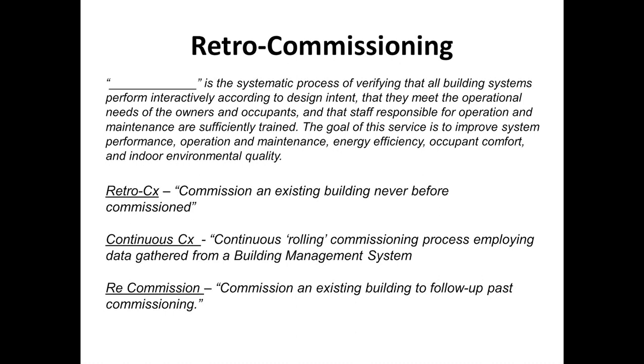There's continuous commissioning, and that's implementing a rolling commissioning process, such as using a building management system or trending data to really keep track of implementations that have been made and continuously make improvements in a building. And then there's recommissioning of a building. That's a building that's already been commissioned, and looking back at those original commissioning reports, recommissioning the building and getting the building back away from that operational drift back onto the original design for the building.